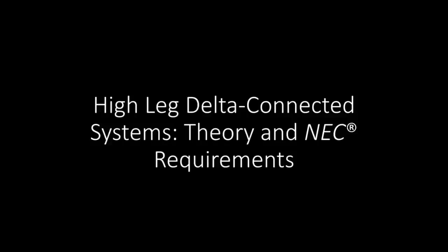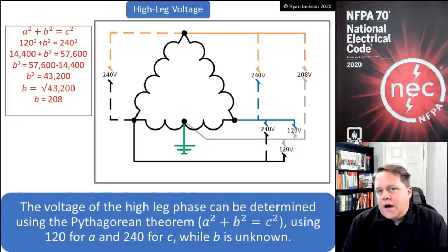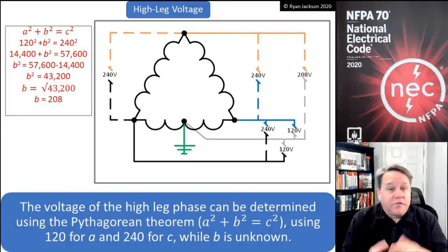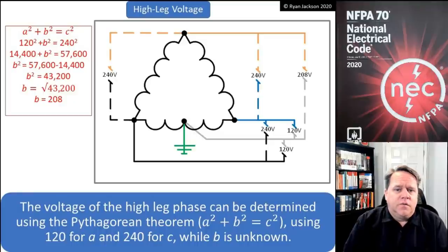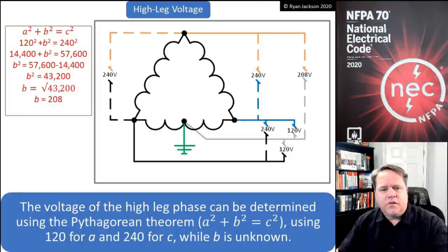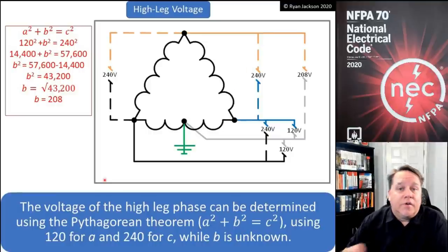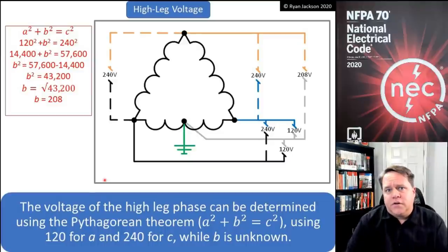Hello everyone, hope you're doing well. Ryan Jackson here. Today we're going to be talking about high leg connected systems theory and NEC requirements. A high leg Delta — first thing to understand is that it is a Delta; there's no such thing as a high leg on a Y connected system. What we're looking at here is a Delta connected transformer, and what makes this a high leg is the grounding configuration.